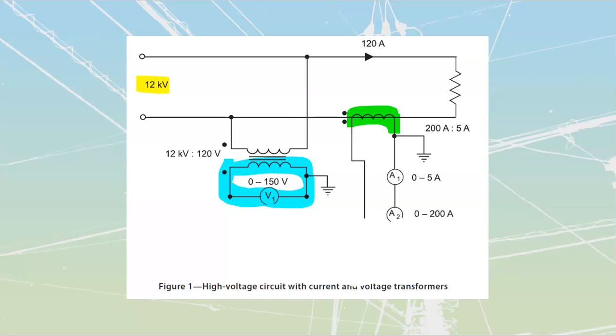That 120 volt secondary is going to be placed over top of a meter that is rated from 0 to 150 volts. And so I'm going to go and read 120 volts on there anytime that I would have 12 kV on there. You'll also note that the secondary of this PT is going to be grounded. We're able to ground any single installation at least once. Usually in only one line. Sometimes there have been multiple points allowed in the past, but that's changing.